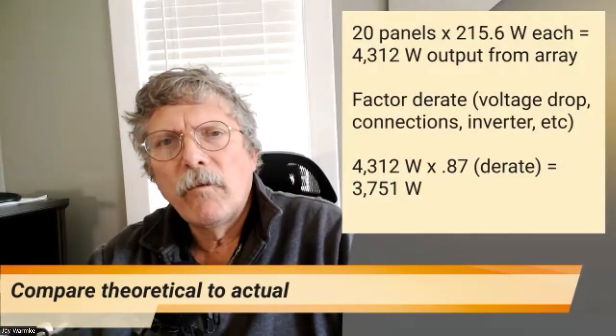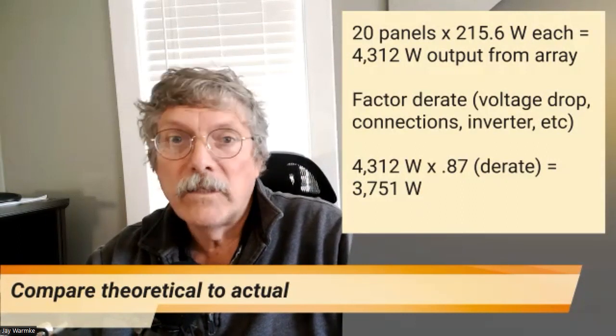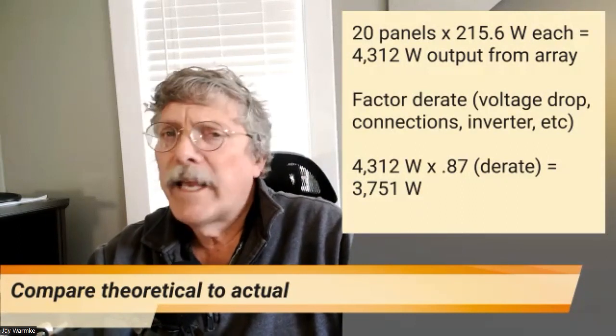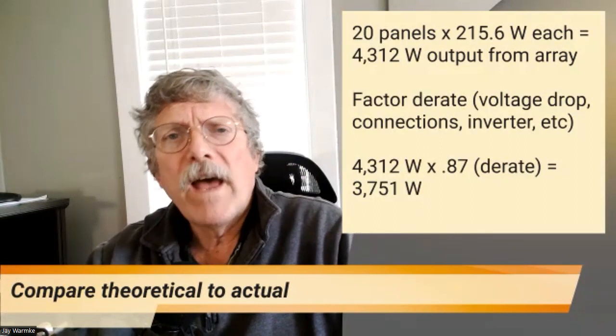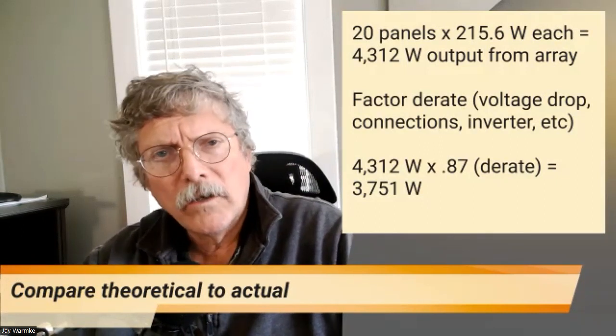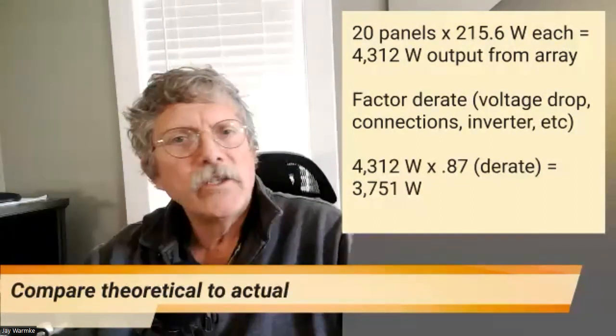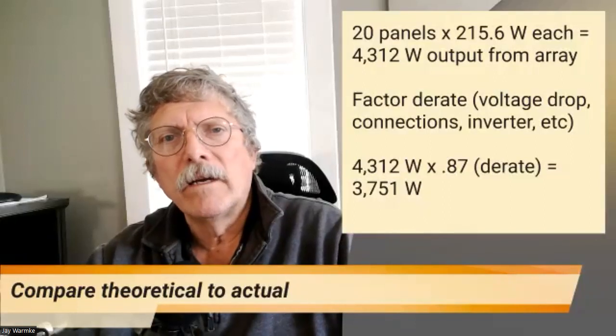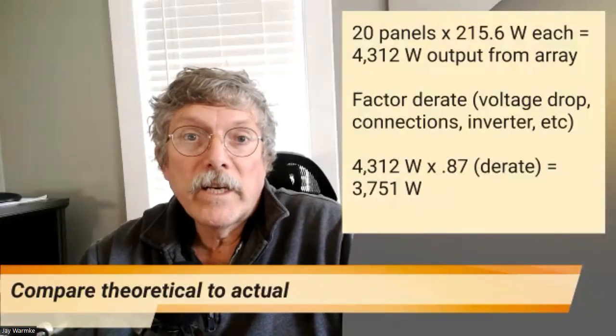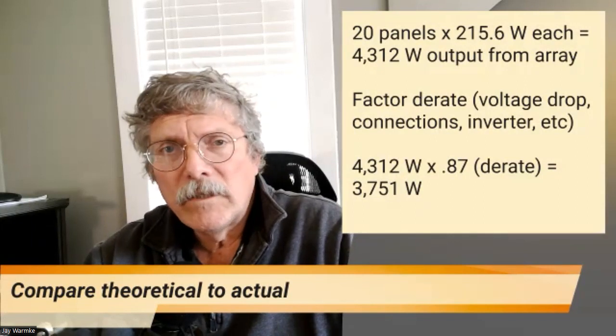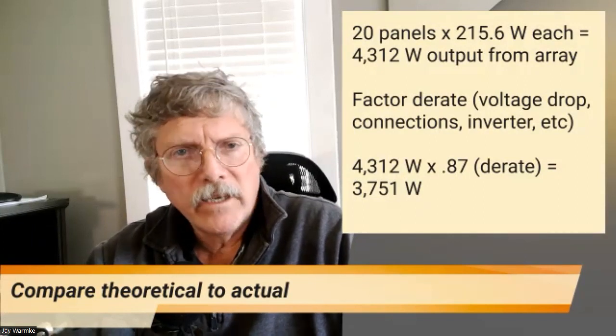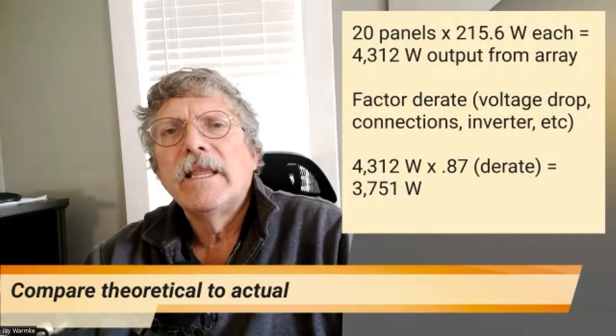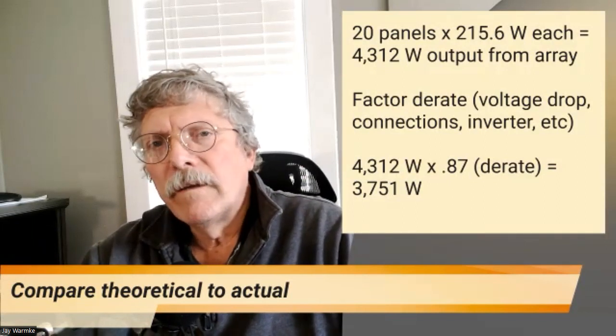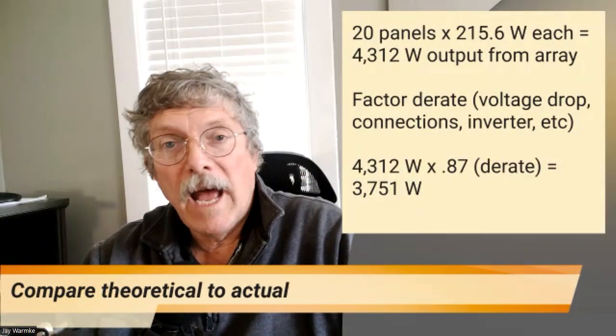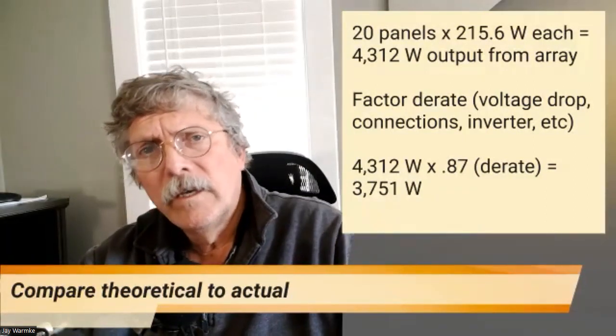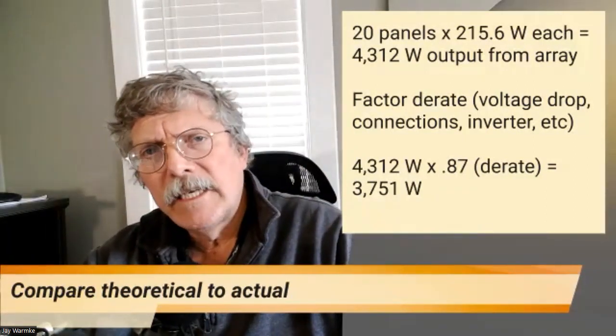So voltage drop, we want to keep to less than 2%, ideally. You can never get it to 0. And that's a factor of how big is the wire, how long are the runs. Other issues that will come into play are going to be losses due to connections. Every time you put some sort of switch or disconnect in there, you're going to have a little bit of loss in there. And then, of course, the other major one is going to be how much is lost through the inverter as we're going from DC to AC.